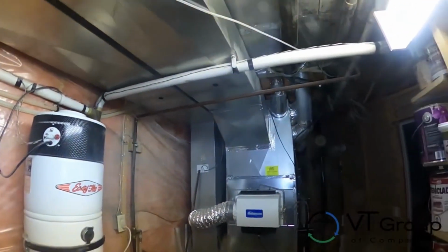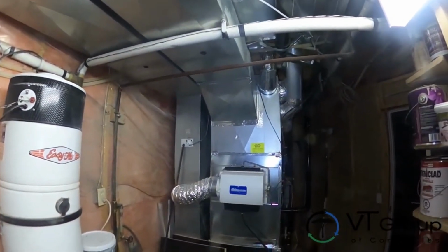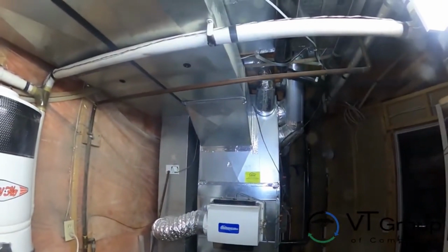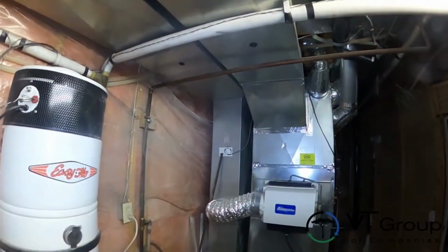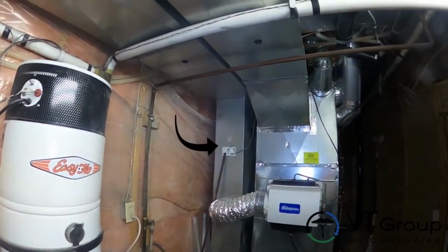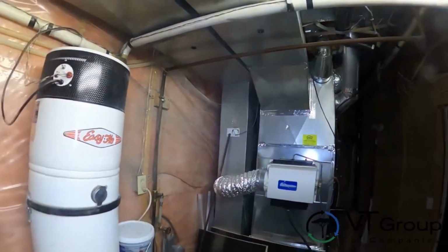That's the back side of the furnace. On the right hand side is the supply air. That's where the humidifier is connected to. You can see the supply air comes off, and then on the left hand side that is the return air, and in this case the humidistat has been connected on the return air because that gives us a better average humidity of the home. So not a bad place to connect it.